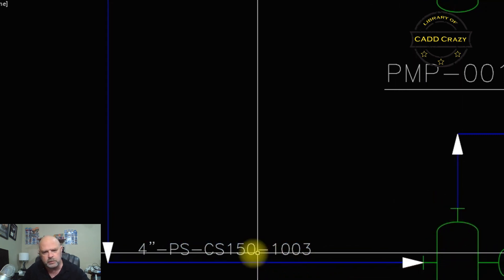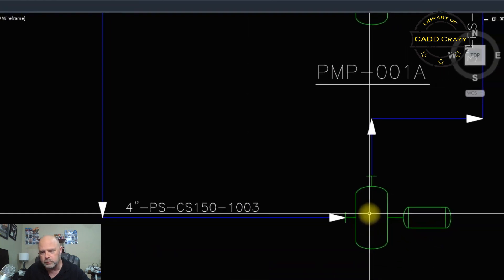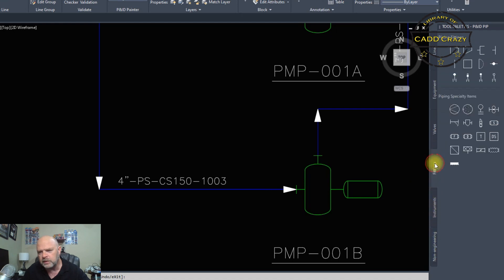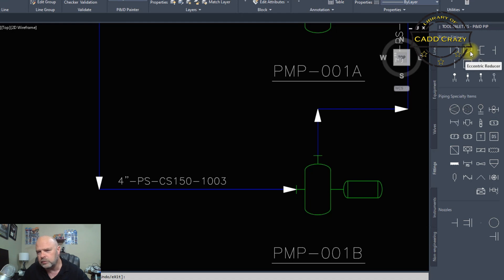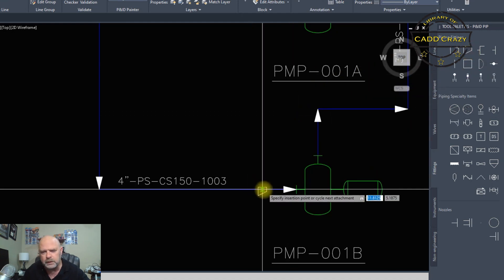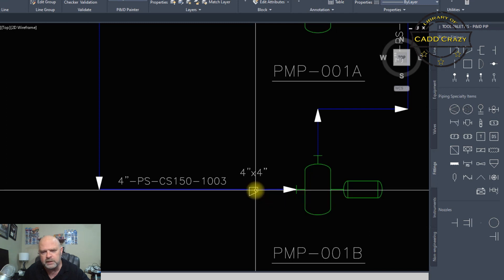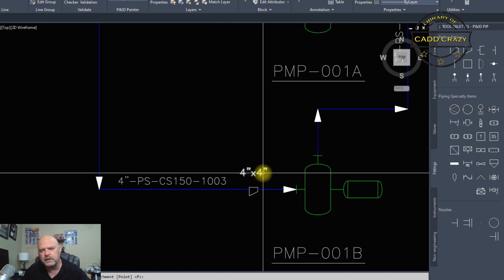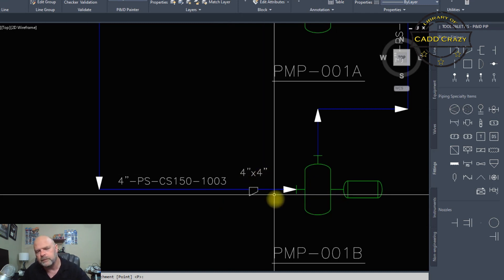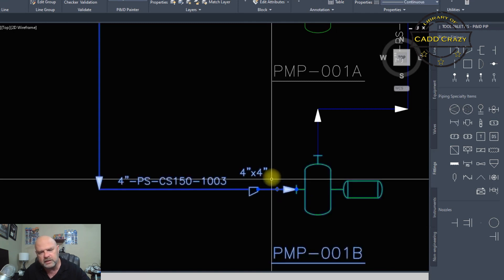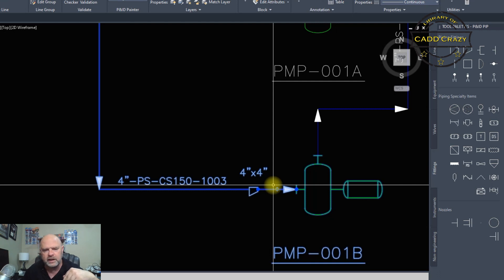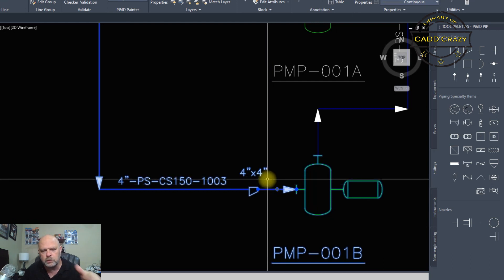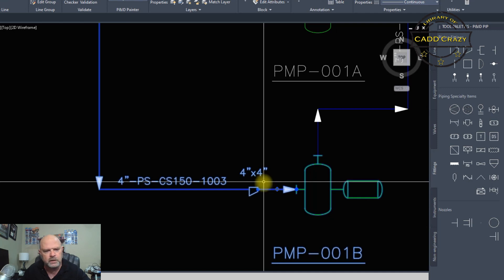One thing you can probably tell about this pump is that we have no reducer. So we're going to change that — we're going to add a reducer here. Go back to our tool palettes, go to fittings, pipe fittings. There are our reducers — you've got a concentric reducer and an eccentric reducer. We're going to click on eccentric and select right there. Now you see it's four by four — that doesn't make any sense, why would you have a four by four reducer? So a reducer is a line segment breaker — it allows you to make changes to one side without affecting the other side.